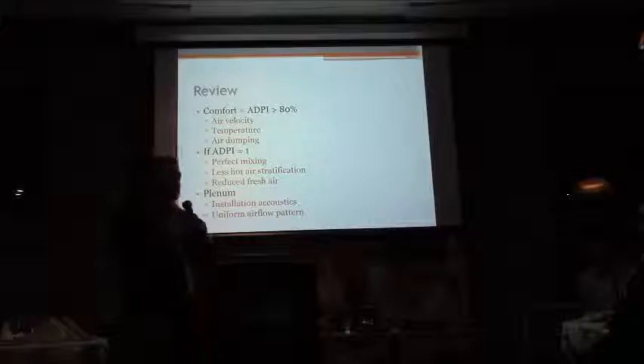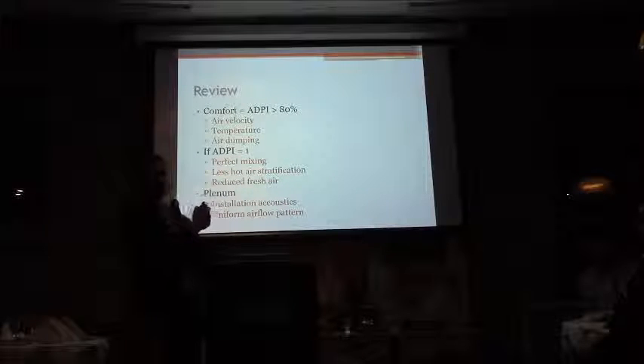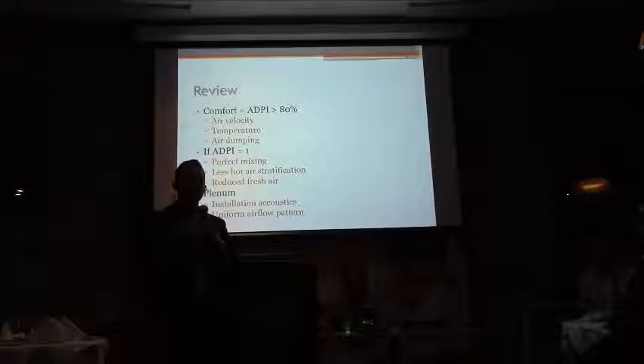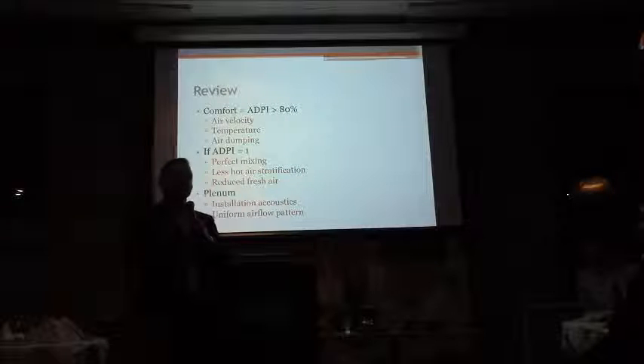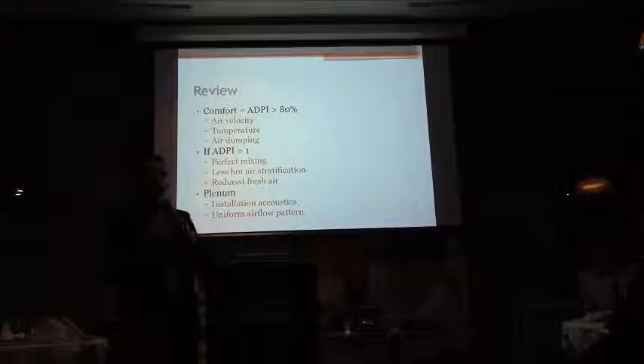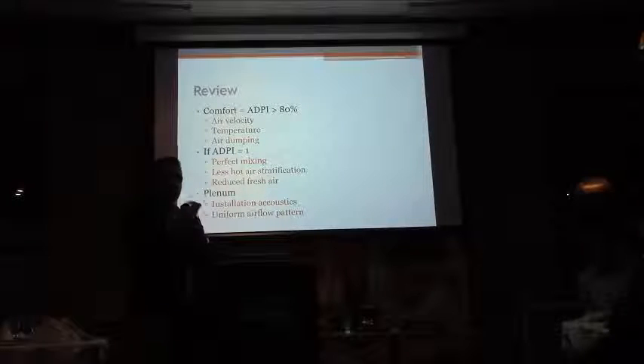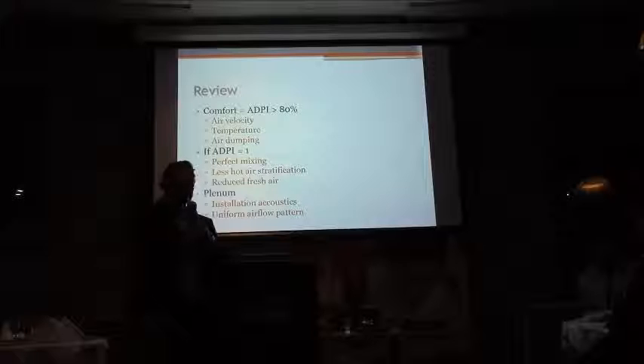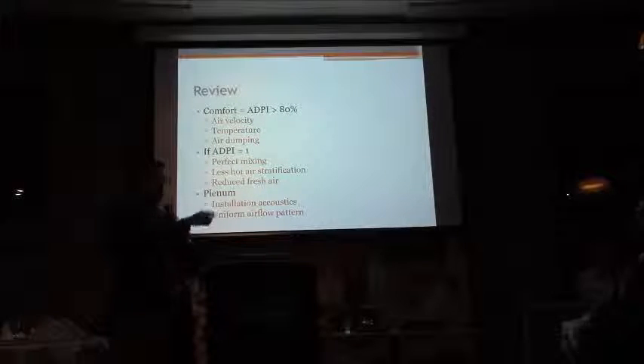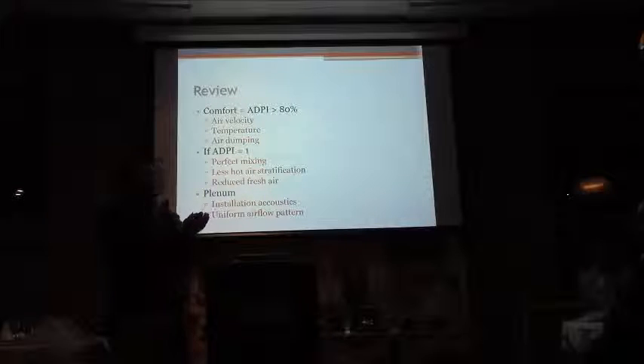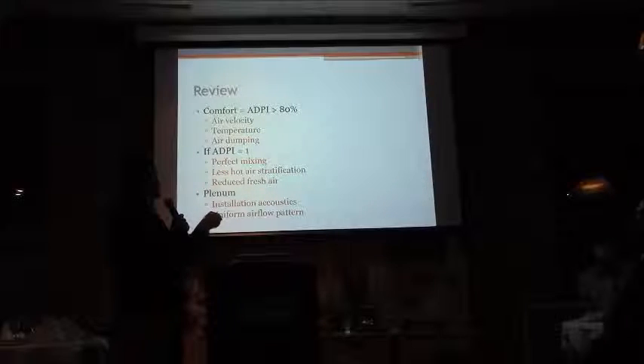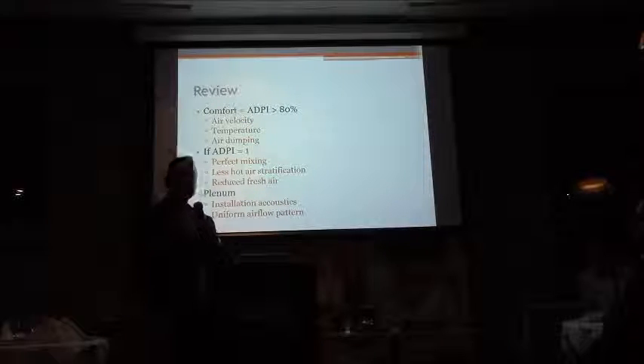If your ADPI is equal to 1, I didn't mention that one, but ADPI equal to 1 is actually the equivalent of saying it's perfect mixing. This is something that's accepted in the industry. If your ADPI is 1, you can consider that you have a perfect mixing scenario. And like I showed in the first slides where I took the most critical spot and we still had a pass at the effective draft temperature. So if you pass there, you pass everywhere and your ADPI is 1 automatically. So that means you have perfect mixing. You have less hot air stratification and you can reduce the amount of fresh air that you're bringing into your building.